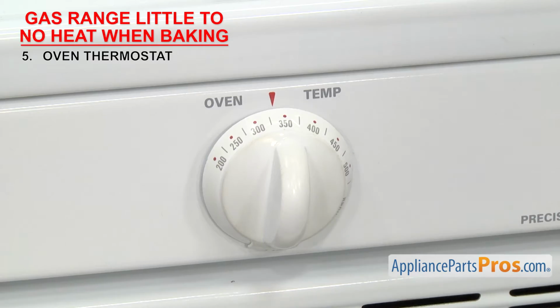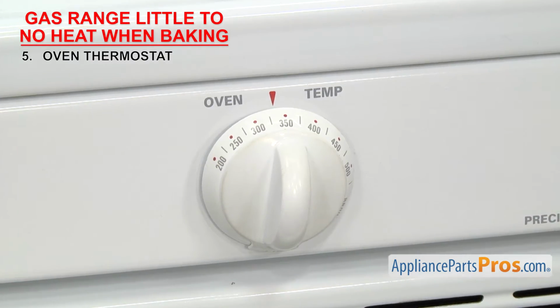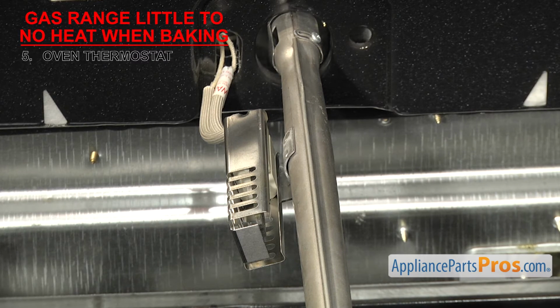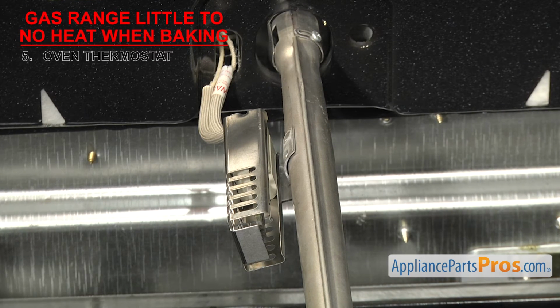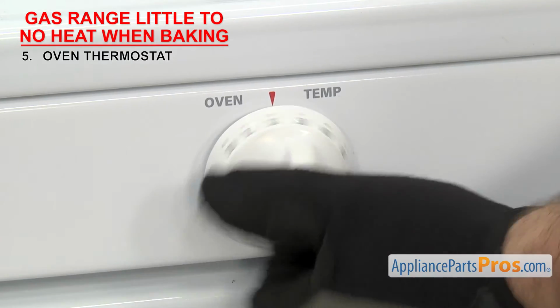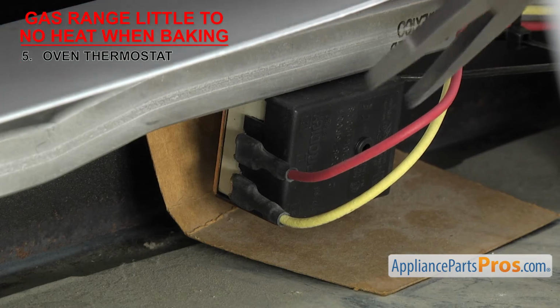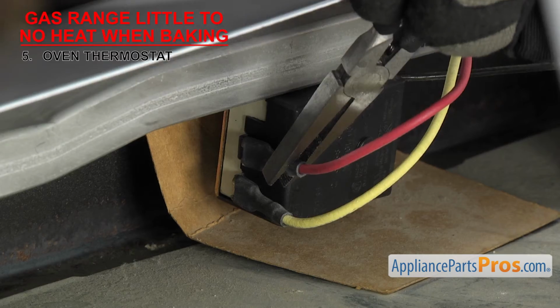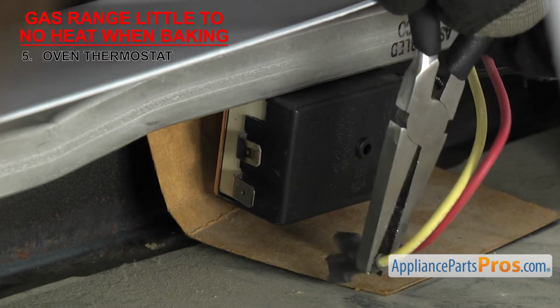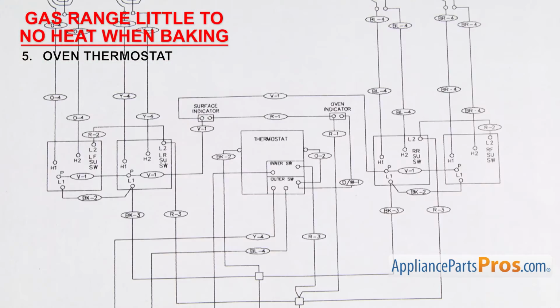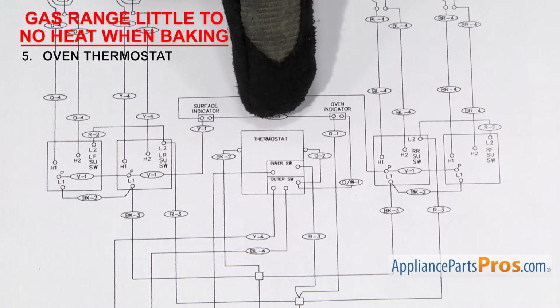The other way it could fail is if the contacts inside are going bad and power isn't being sent to the igniter when the thermostat is turned on. In order to check that, we'll have to test the thermostat for continuity. Normally there are only 2 wires you'll need to remove.